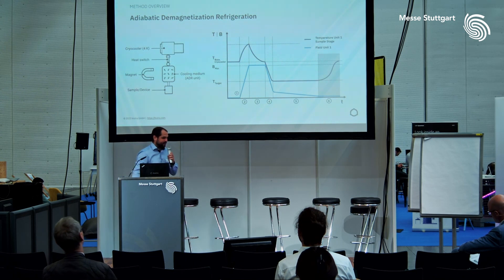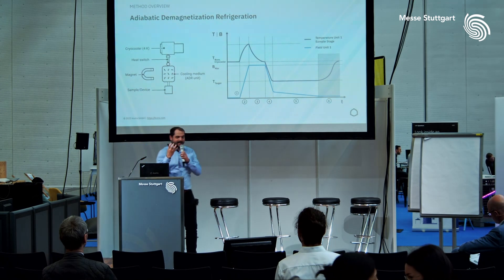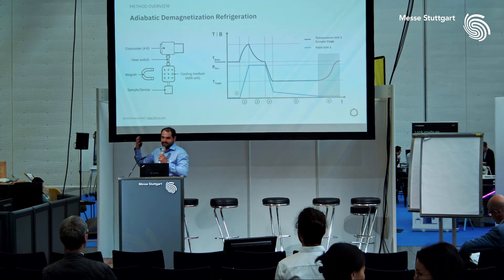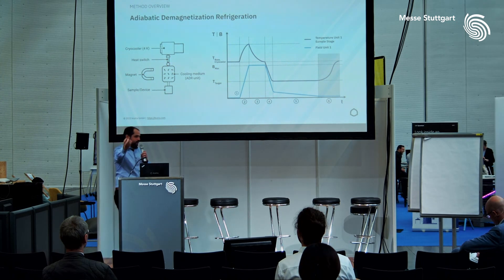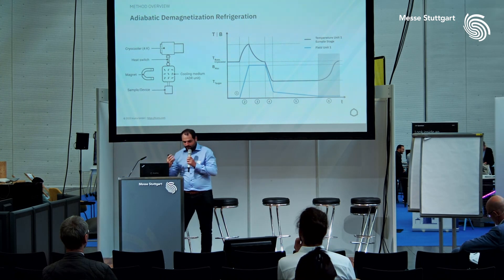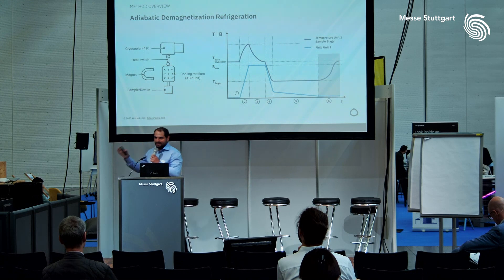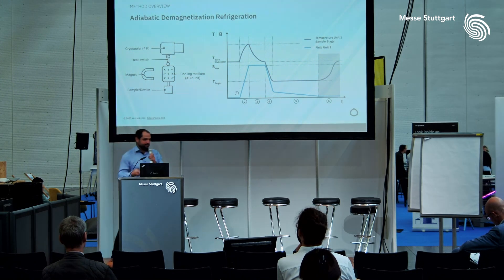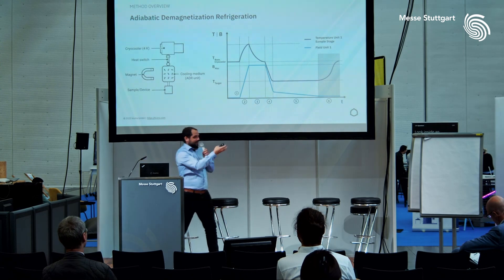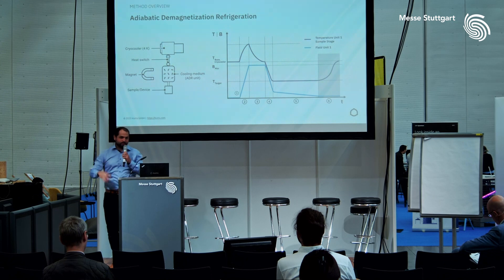Once the heating is dissipated, we open the heat switch, placing our ADR unit in an adiabatic condition — isolated from the thermal bath. As we remove the magnetic field, the spins in our paramagnet want to disorder, and the only place they can take this entropy is from the thermal entropy of the system. So as the magnetic field is ramped down, the temperature also comes down, giving us cooling power.